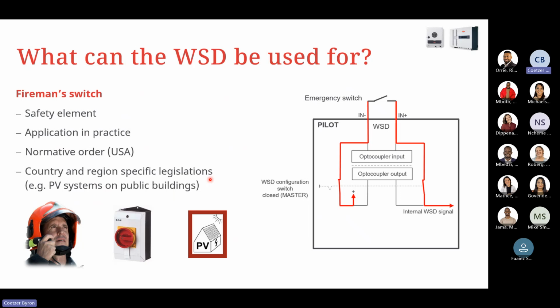So again, what can the WSD be used for? It's used as a fireman switch. It can be for a safety element, so application in practice. This has become a normative order in the USA, and country and region specific legislations require that you have an e-stop that can trigger the inverters to shut down, whereas we will typically trigger, for example, the AC isolators to then open, causing the inverters to go into an idle state. So it's just different legislations regarding the safety devices.